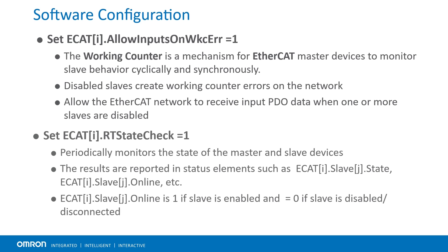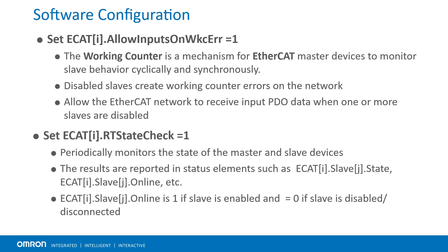Second, set ECAT[0].RTStateCheck to 1. This parameter periodically monitors the state of the master and slave devices on the network. The results are reported in status elements such as ECAT[i].slave[j].state and ECAT[i].slave[j].online.